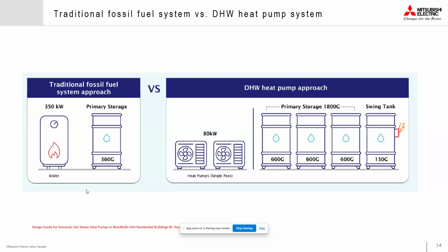But by doing that, you have to have higher storage capacity. So that capacity from 360 gallon, now it increased to 18 or 1900 gallons, almost 3 or 4 times more. So that's how you will design the new system if you want to use your hot heat pump as a water heater.